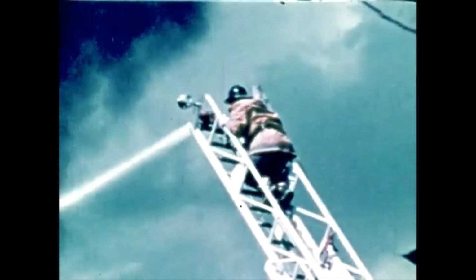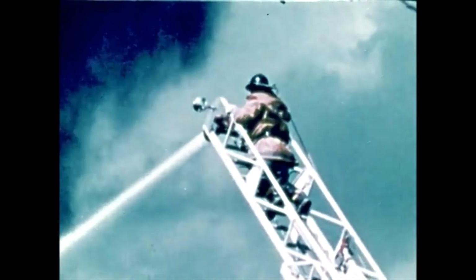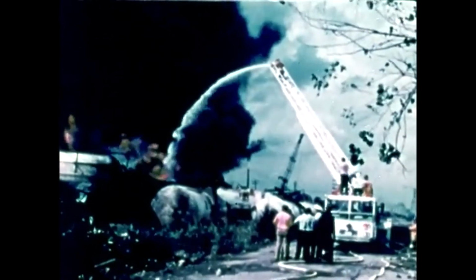How much water is available? The application of water can keep tank metal at safe temperatures, but only if large volumes can be delivered to all points of flame contact. Water application may need to be sustained for several hours. Fire officers are advised to assess carefully the danger to emergency personnel before making a commitment to fighting a fire involving serious BLEVE hazards.